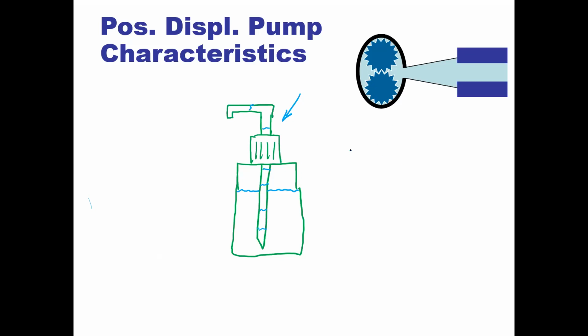Centrifugal pumps do not self-prime. Think back to that chart - when we close off and have a no-flow scenario, are we moving gallons per minute? No, we're not. We're stationary at a certain pressure, but we're not physically moving a fixed volume. So centrifugal pumps are not self-priming. They need to be filled with whatever fluid they're going to be sucking, all the way down to that suction pipe.